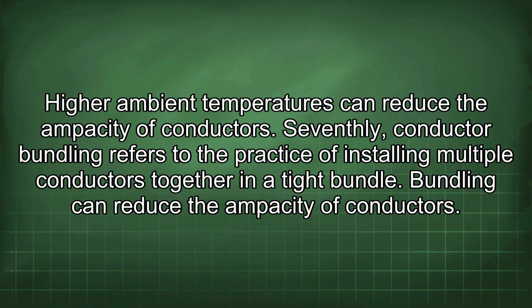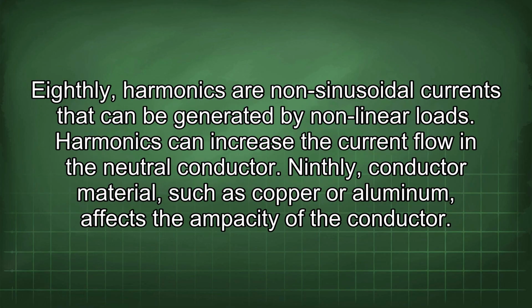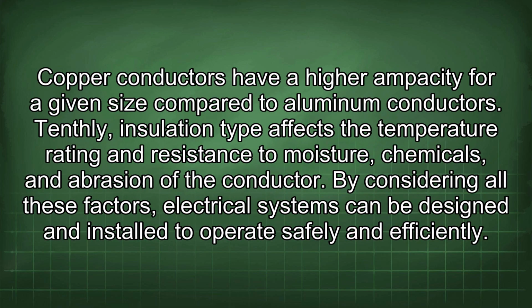Seventhly, conductor bundling refers to the practice of installing multiple conductors together in a tight bundle. Bundling can reduce the ampacity of conductors. Eighthly, harmonics are non-sinusoidal currents that can be generated by nonlinear loads. Harmonics can increase the current flow in the neutral conductor. Ninthly, conductor material such as copper or aluminum affects the ampacity of the conductor. Copper conductors have a higher ampacity for a given size compared to aluminum conductors. Tenthly, insulation type affects the temperature rating and resistance to moisture, chemicals, and abrasion of the conductor. By considering all these factors, electrical systems can be designed and installed to operate safely and efficiently.